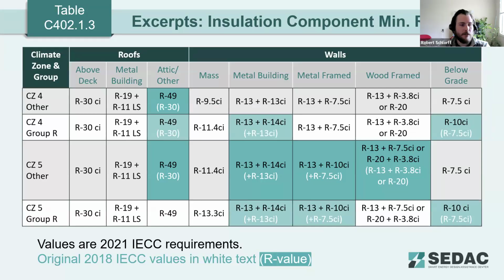All right, moving into the insulation tables for exterior assemblies, or for thermal envelope assemblies. On the screen here, we've recreated a portion of C402.1.3. The highlighted cells represent cells that have had their requirements increased or changed since the last code cycle. The 2018 IECC values are shown there in the white text with brackets. As we can see, the roof insulation value for attics has been increased. It is now R49 in all climate zones and groups. Metal buildings have also had their continuous insulation requirements increased, along with metal framed walls. Again, the continuous insulation requirement has been increased there.